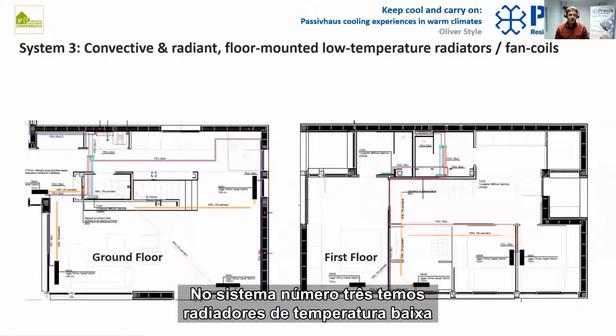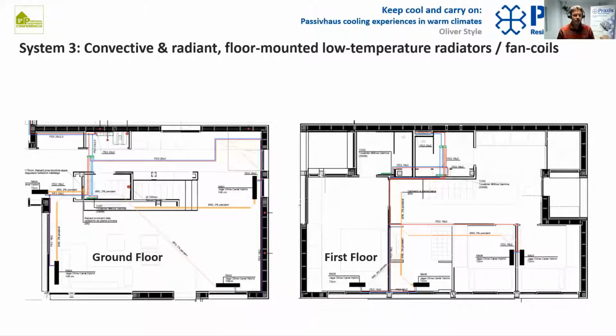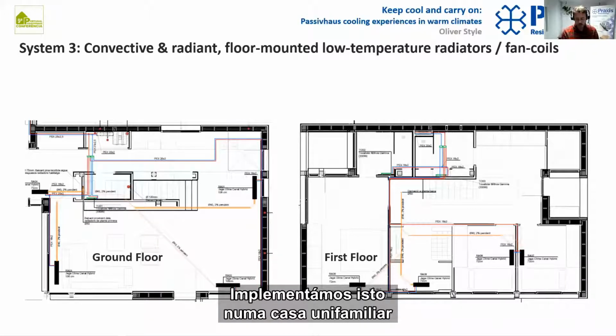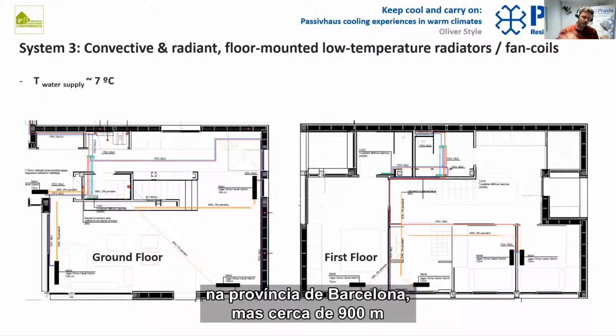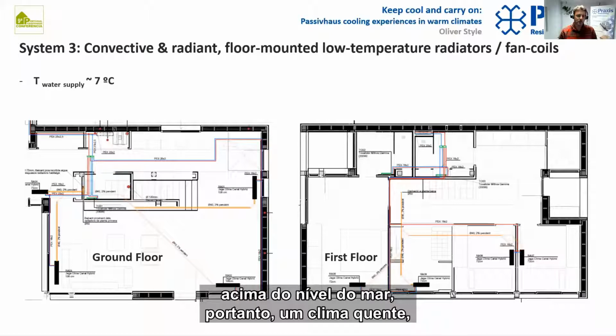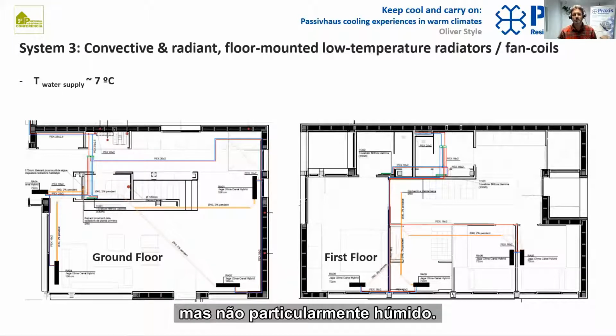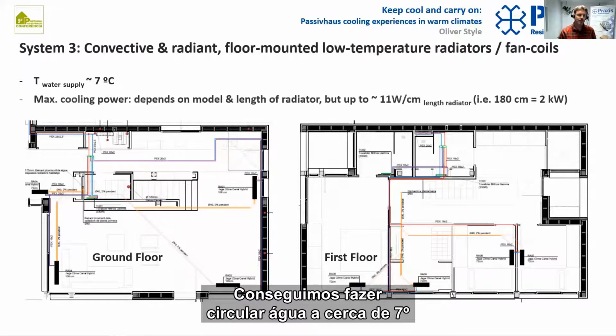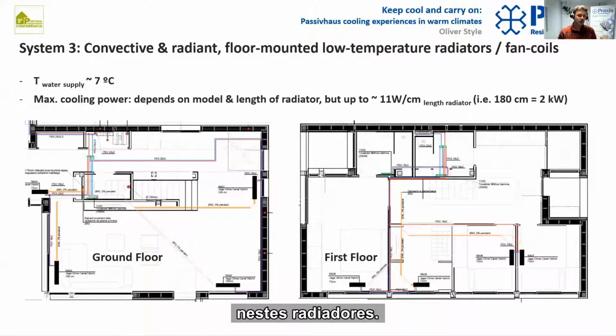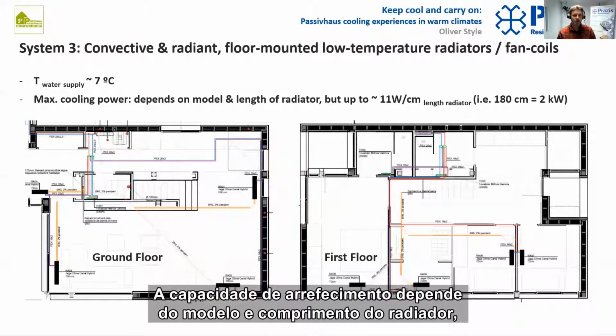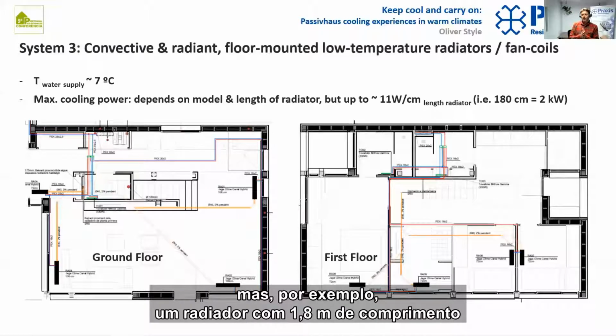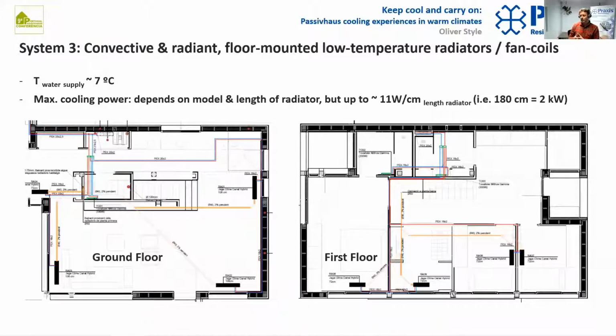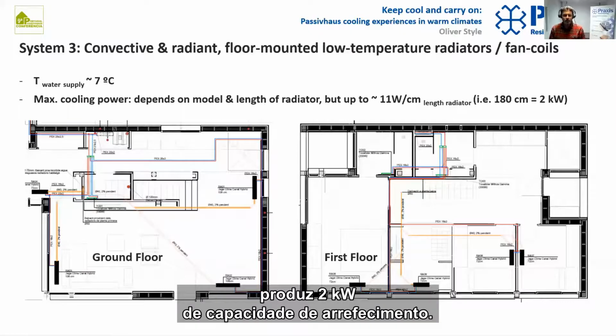System number 3. So these are floor-mounted low-temperature radiators or fan-coils. So we implemented this in a single-family home in the province of Barcelona, but about 900 meters above sea level. So a warm but not especially humid climate. We can run water temperature supply at about 7 degrees on these kind of radiators. So the maximum cooling power depends on the model and length of the radiator. But to give you an example, a radiator about 1.8 meters long will give you about 2 kilowatts of cooling power.